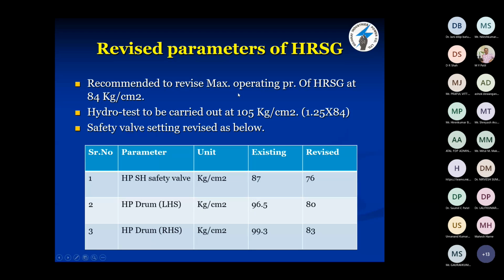Similarly, from station 1, you have to revise the maximum operating pressure of HRSG. After revision, it was 84 kg. So hydro test was to be carried out at 105 kg, and safety valve settings were also to be revised. These are the settings of safety valve. This is HP safety valve, HP superheater safety valve. Existing was 87 kg and revised is 76 kg.